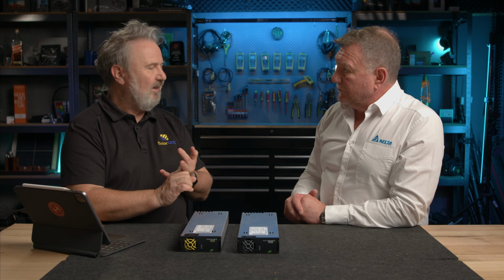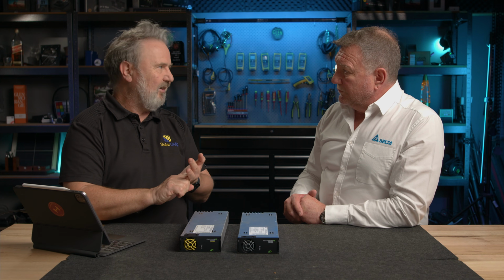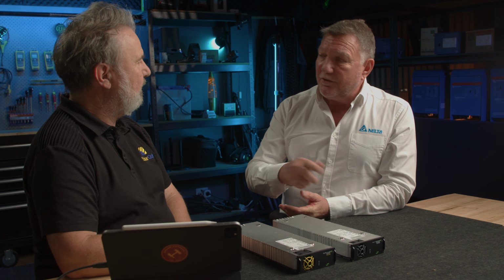So you've got solar, which is intermittent and daytime only, battery storage to supplement when there's no solar, and if either of those two aren't working because it's nighttime and the battery's discharged, the generator can come to the rescue. Or if you've got great weather and the battery's only required late at night but you want to check the generator turns on, we can also set it up so the generator runs intermittently.